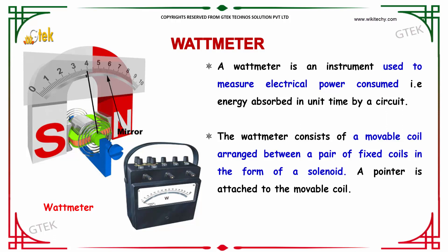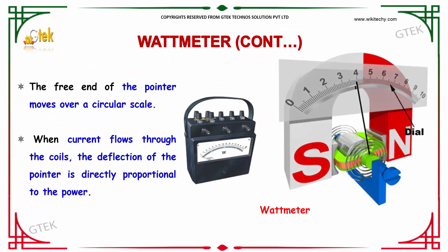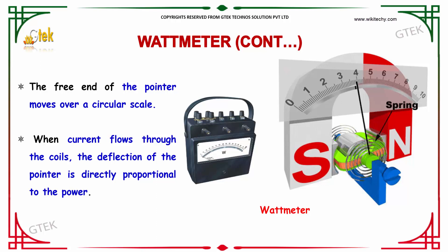A wattmeter consists of a movable coil arranged between a pair of fixed coils in the form of a solenoid. A pointer is attached to the movable coil, and its free end moves over a circular scale. When current flows through the coil, the deflection of the pointer is directly proportional to the power.